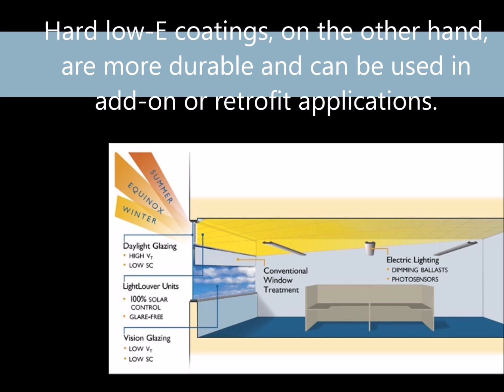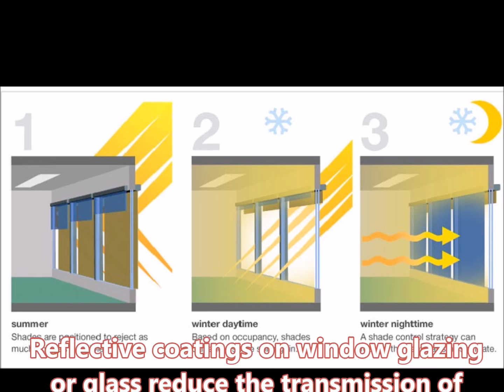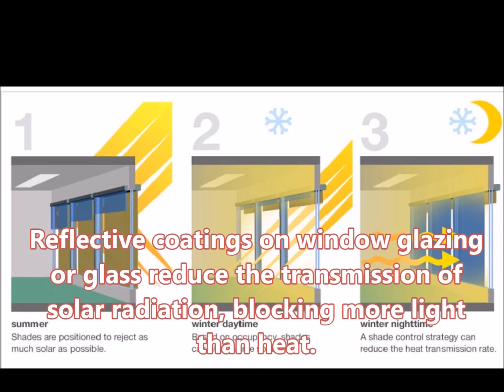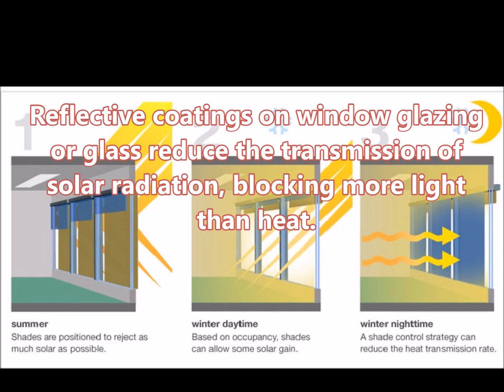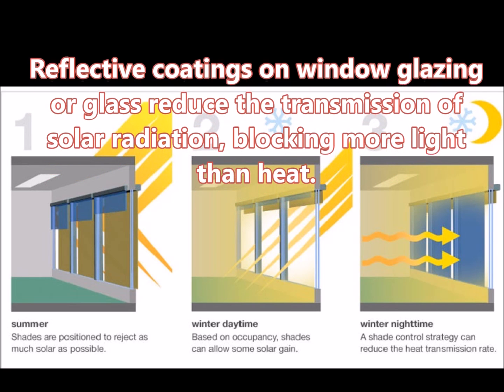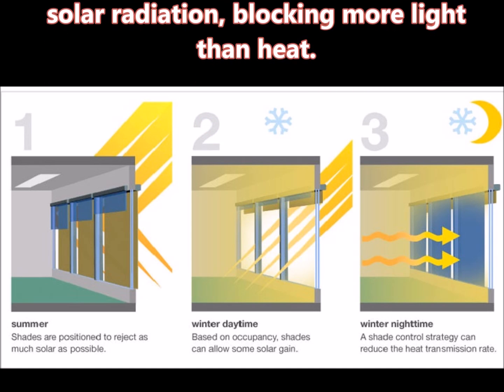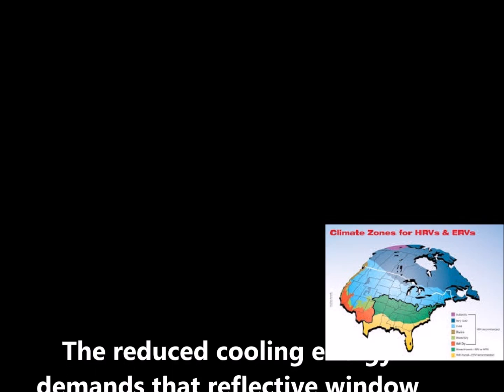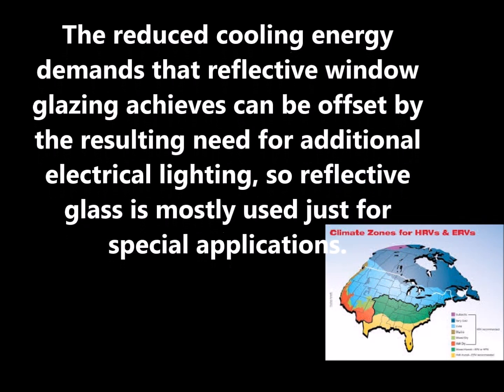Let's look at reflective window glazing or glass. Reflective coatings on window glazing or glass reduce the transmission of solar radiation. They block more light than heat; therefore, they greatly reduce a window's visible transmittance or VT and glare, but they also reduce a window's solar heat gain coefficient or SHGC. Reflective coatings usually consist of thin metallic layers and come in a variety of metallic colors, including silver, bronze, and gold. Reflective window glazing is commonly used in hot climates where solar heat gain control is critical; however, the reduced cooling energy demands they achieve can be offset by the resulting need for additional electrical lighting, so reflective glass is mostly used just for special applications.